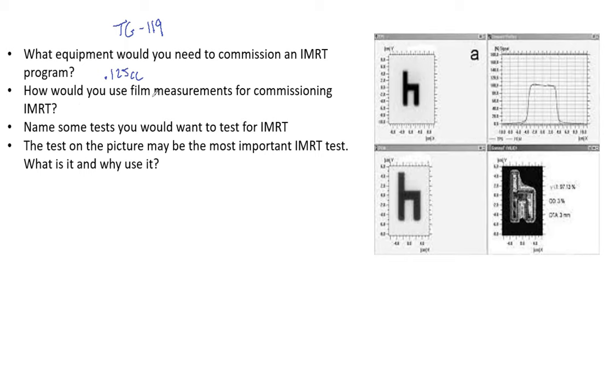You should know this very well: use three percent, three millimeter — get it as best as you can. Ideally you want 95% or more of points passing when you do that gamma analysis.